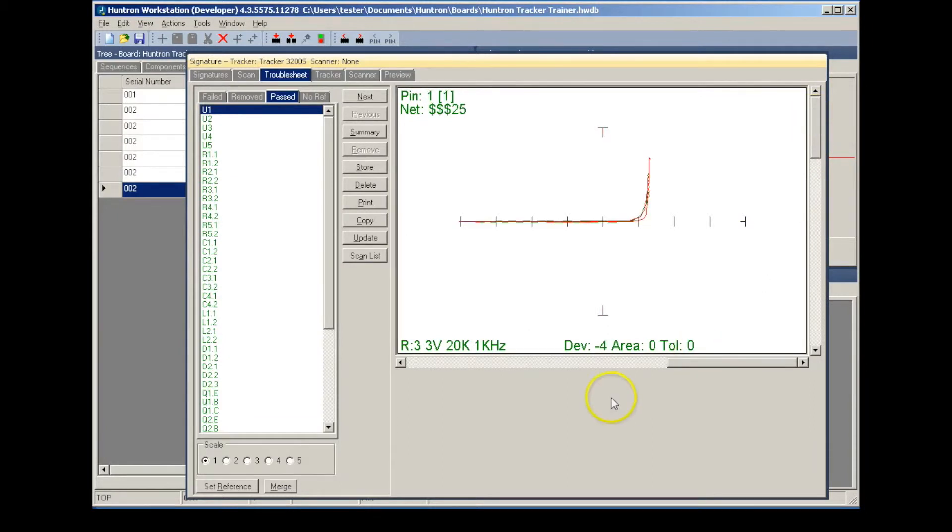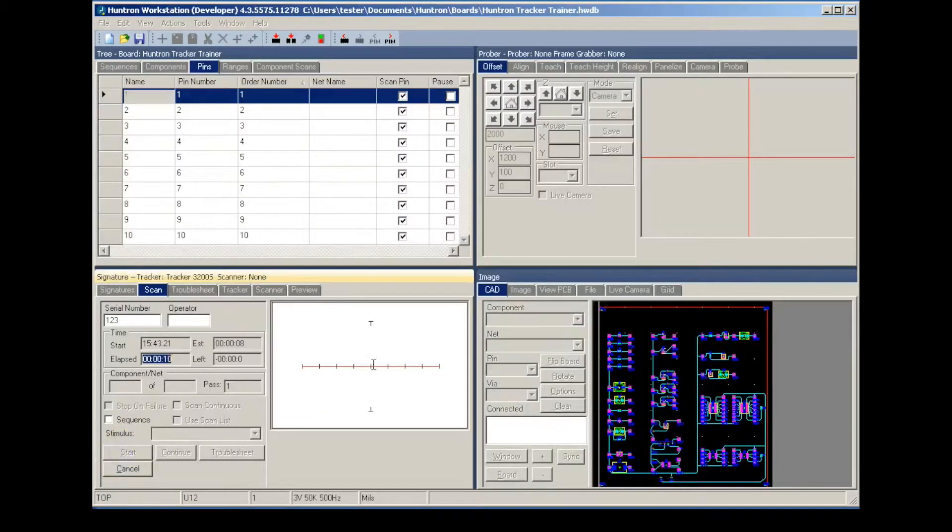The tracker is controlled through a USB port. Scanning a component is fast and storing component signatures into a PCB database eliminates the need for a known good comparison board.